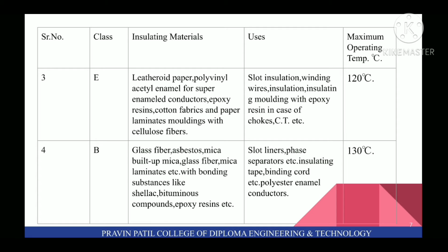For class B insulation, insulating materials are glass fiber, asbestos, mica, built-up mica, glass fiber, mica laminates, etc., with bonding substances like shellac, bituminous compounds, epoxy resins, etc. Uses are slot liners, phase separators, etc., insulating tape, binding cord, etc., polyester enamel conductors, and maximum operating temperature is 130 degrees Celsius.